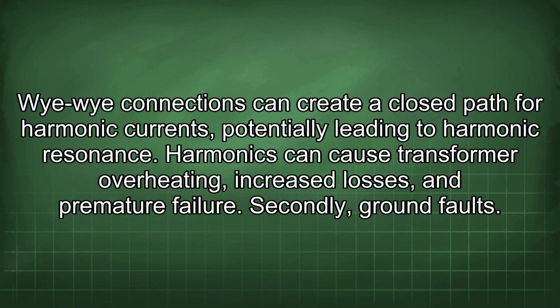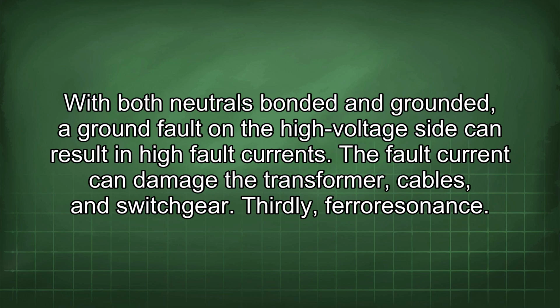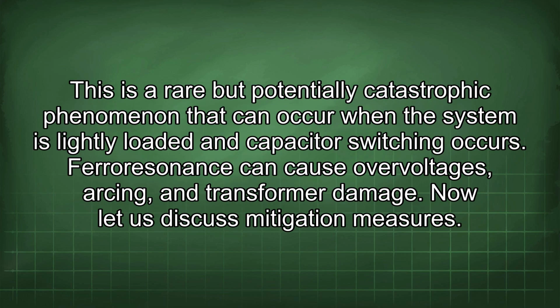Secondly, ground faults. With both neutrals bonded and grounded, a ground fault on a high voltage side can result in high fault currents. The fault current can damage the transformer, cables, and switchgear. Thirdly, ferroresonance. This is a rare but potentially catastrophic phenomenon that can occur when the system is lightly loaded and capacitor switching occurs. Ferroresonance can cause overvoltages, arcing, and transformer damage.